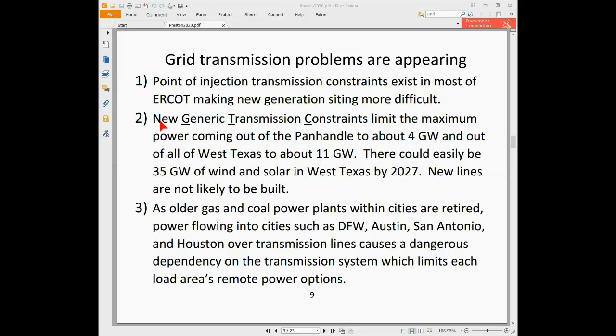Now ERCOT is doing a new kind of study called the Generic Transmission Constraints Limits. These are stability studies where they look at the grid in little time slices, and they consider various problems that might happen, like a transmission line being outaged. If they find the grid starts oscillating in an unstable manner, and this oscillation worsens if there's too much power flowing on the transmission lines, they have to put a constraint on the amount of power flowing through the transmission system.